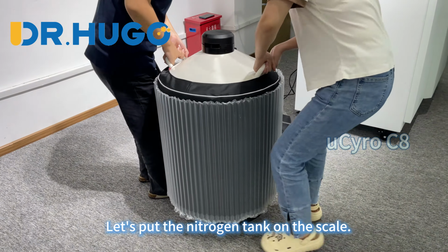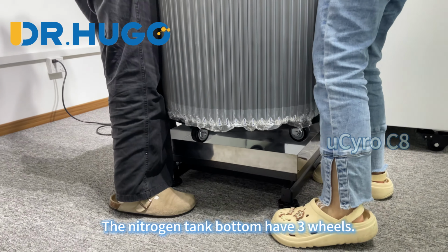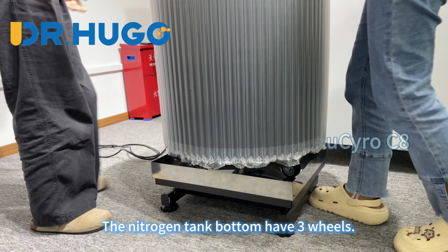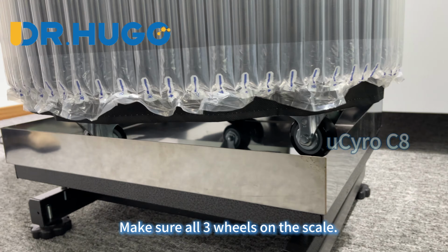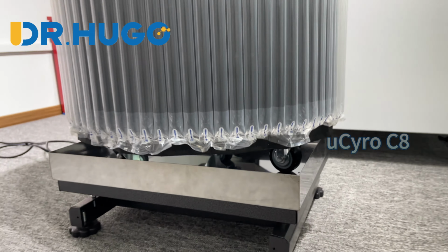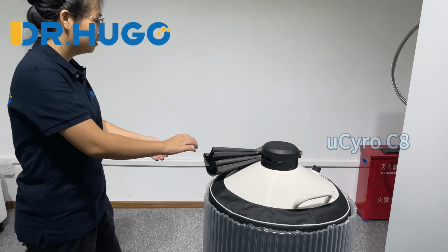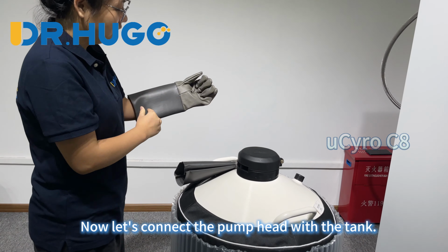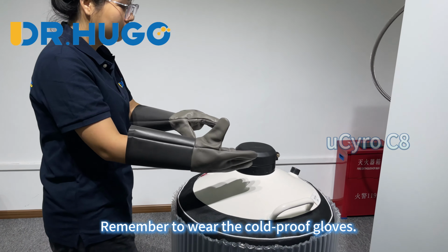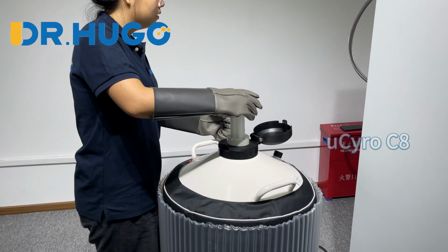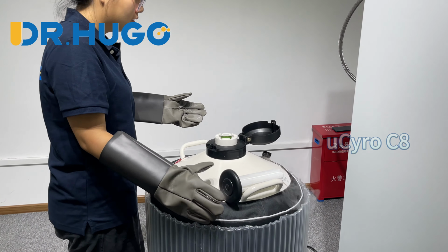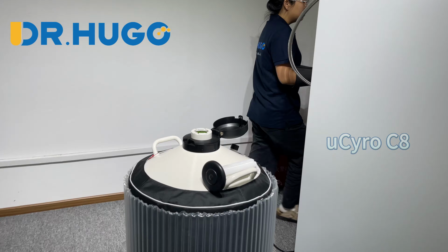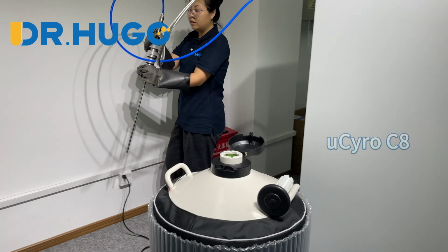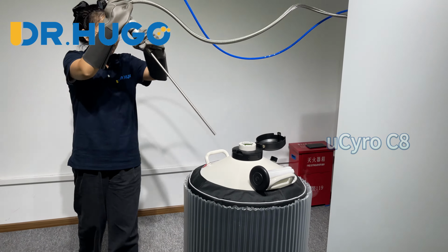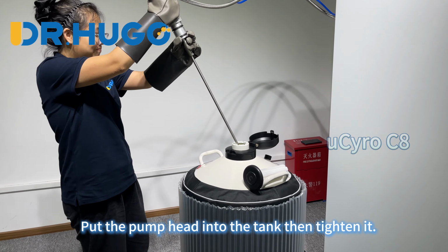Let's put the nitrogen tank on the scale. The nitrogen tank bottom has 3 wheels. Make sure all 3 wheels are on the scale. Now let's connect the pump head with the tank. Remember to wear the cold-proof gloves. Put the pump head into the tank, then tighten it.